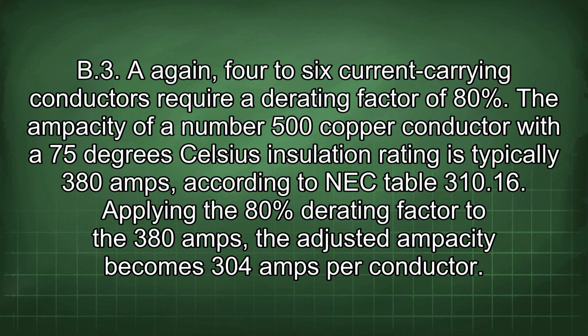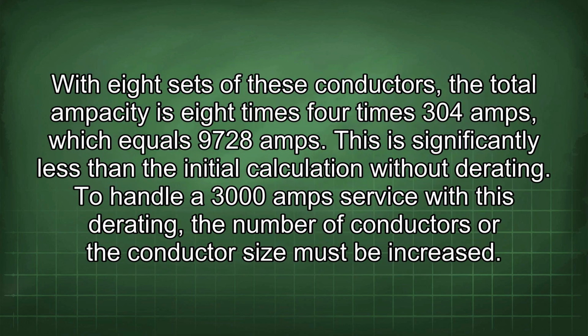The ampacity of a number 500 copper conductor with a 75 degrees Celsius insulation rating is typically 380 amps, according to NEC table 310.16. Applying the 80% derating factor to the 380 amps, the adjusted ampacity becomes 304 amps per conductor. With 8 sets of these conductors, the total ampacity is 8 times 4 times 304 amps, which equals 9,728 amps. This is significantly less than the initial calculation without derating.